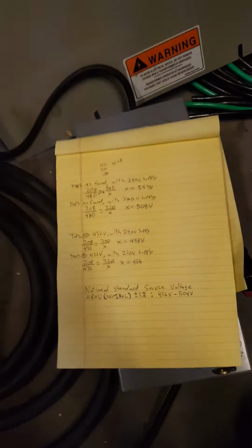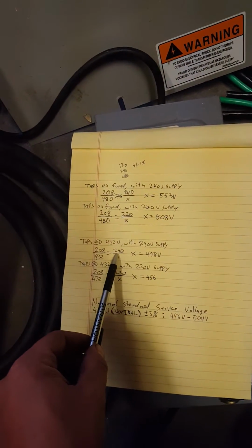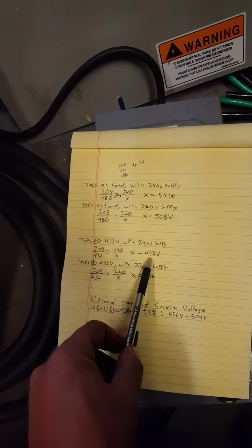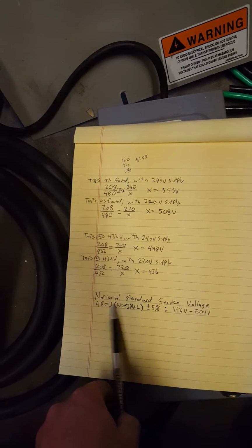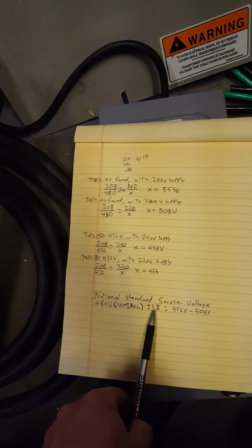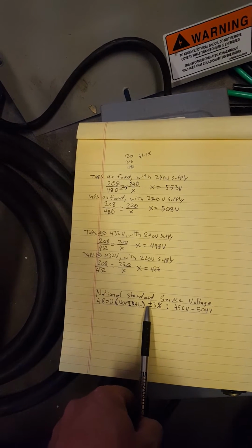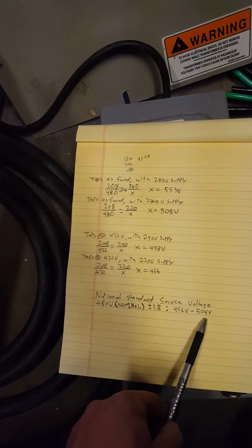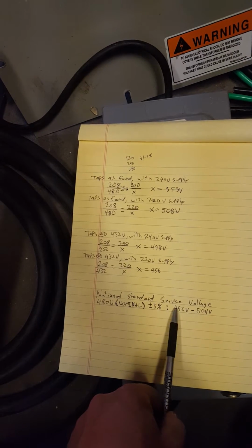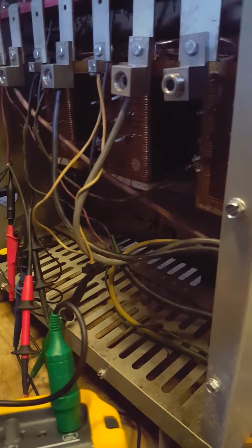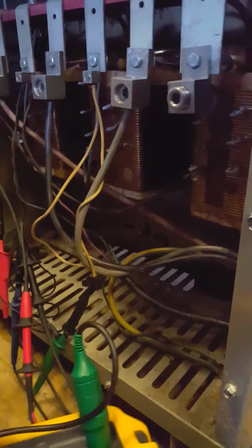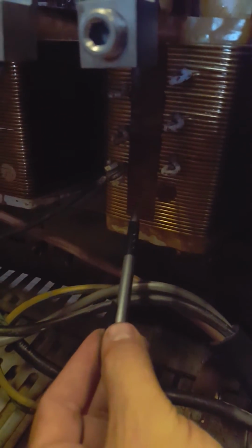But the 220 here is what lends to the workable voltage. If I went up to 240, which I will, I ought to get 498, which is within the national standard of plus or minus 5%. I can be anywhere from 456 to 504. So actually, this transformer should work either in here or in the shop without making any tap changes. See, I was worried that being a 208 volt transformer, I was going to have to splice into these windings here and make my own new tap.